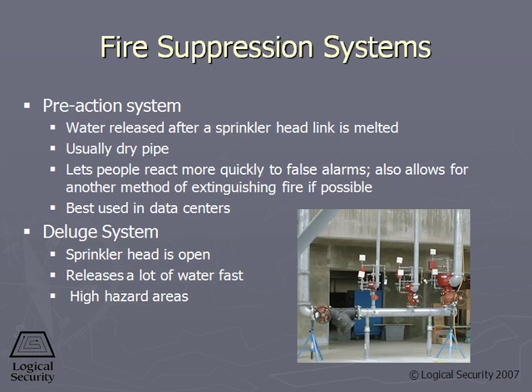The next type of sprinkler system is called the pre-action system. Now, the pre-action system is generally considered to be a combination of the wet pipe and a dry pipe. Generally speaking, we have a dry pipe implementation where a valve is in a thermally controlled area away from the sprinkler heads. And the sprinkler heads additionally have a plastic billet that actually is the plug for the sprinkler. These plastic billets are specially configured or designed so that they melt at a specified temperature. That temperature specification is generally part of the ordinances, the fire regulations for your particular area.